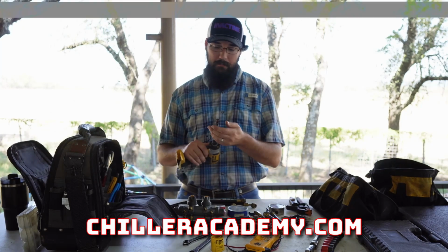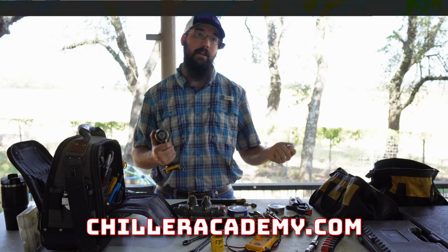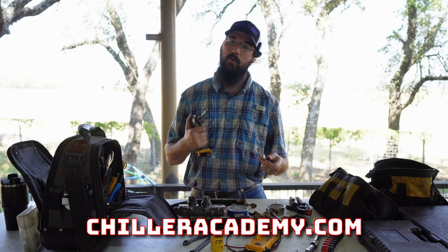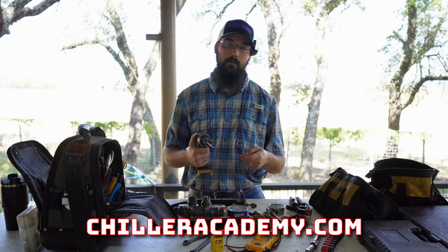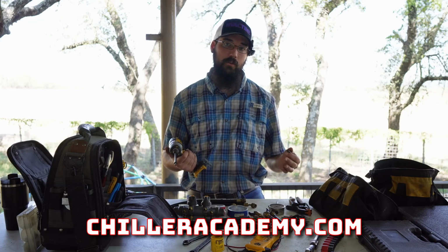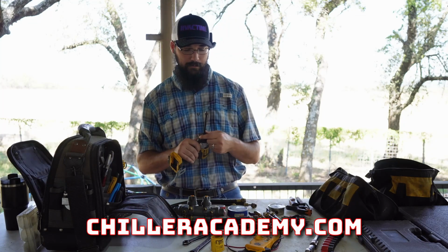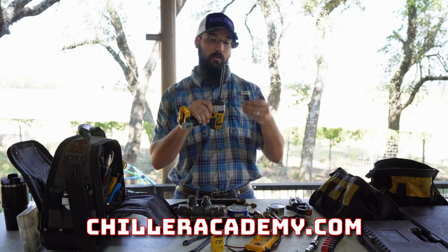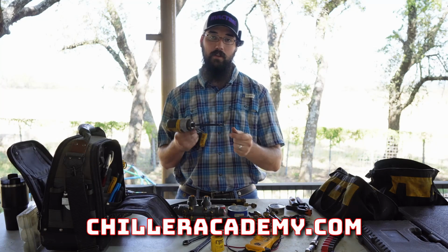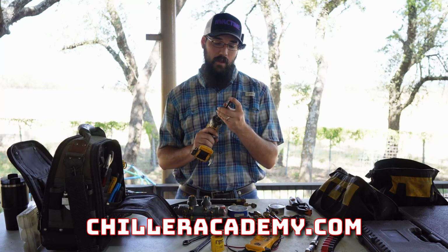Also, having a magnet for sensor activation, specifically if we're working on a Trane 530 system or the newer UC controller line. The Trane UC controllers. You have to have TU software to do it, but these Malco magnetic bits have actually worked really well for me for those Trane sensors. I'll use this to activate the sensor for binding purposes.